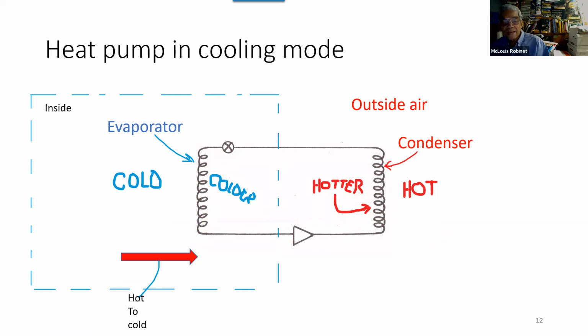And again, it's often a question of how this can work. Say, for example, if this is a hot summer day, if this is 80 degrees, this has to be 90 or more. If this is 110, this is maybe 120 or whatever. So the compressor works harder the higher this gets.